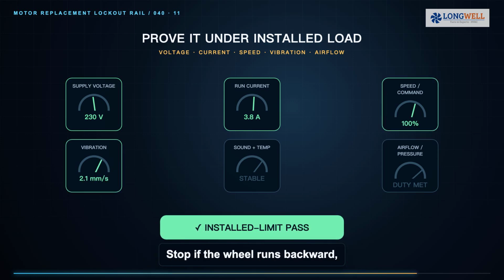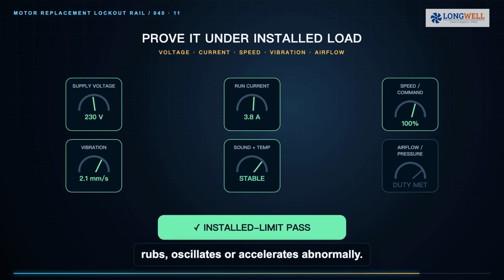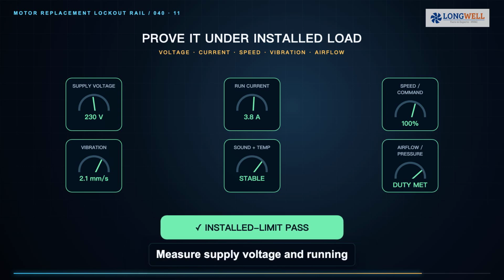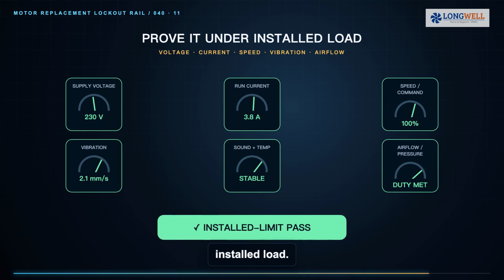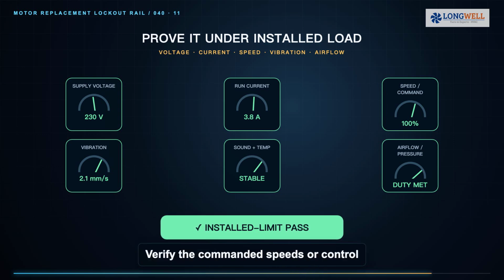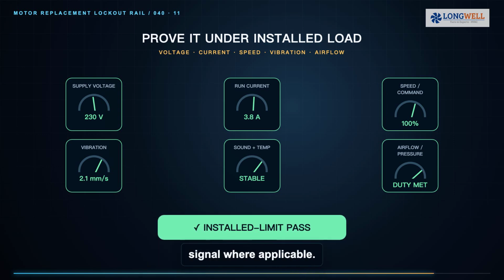Stop if the wheel runs backward, rubs, oscillates, or accelerates abnormally. Measure supply voltage and running current, then compare current with the motor nameplate under the actual installed load. Verify the commanded speeds or control signal where applicable. Check vibration, sound, bearing and motor temperature trend, and airflow or pressure at the unit. A motor that spins is not yet a successful replacement. It must operate within electrical, mechanical, and airflow limits.